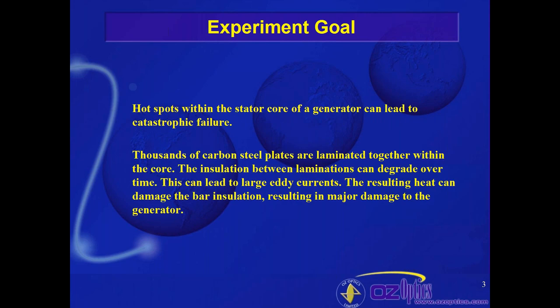Hot spots within the stator core of a generator can lead to catastrophic failure. As you can imagine, things get hot — that's bad. You often get things breaking down because of heat, things expand unevenly, and you can get short circuits if things start to degrade. Inside an electric generator, there are generally thousands of steel plates laminated together within the core. Within the core, these laminated plates have insulation surrounding them, and that insulation normally degrades over time. It's important that this be monitored because if it degrades too far, you get catastrophic failure.